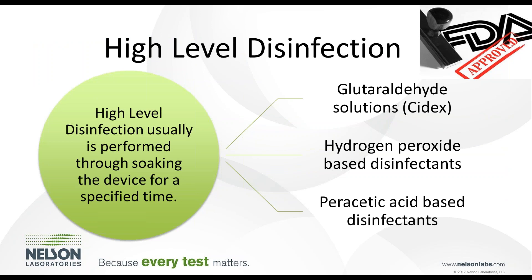For high level disinfection, some chemicals commonly used include glutaraldehyde, which is the most common in the U.S. — Cidex is a common trade name. Hydrogen peroxide and peracetic acid are also used for high level disinfection, and these are typically chemicals used in the European market, whereas glutaraldehyde is predominantly used in the U.S.